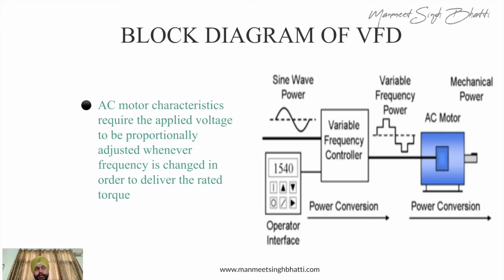But it is okay with the motor, because based on the change in the flux, the motor automatically gets magnetized and starts working on this. The effect of the sinusoidal wave and the not so perfect sinusoidal wave is not very high on the AC motors. So the behavior of the AC motors remains the same as per the requirement, but you also get additional control on the frequency. So this is the way it is going to work.